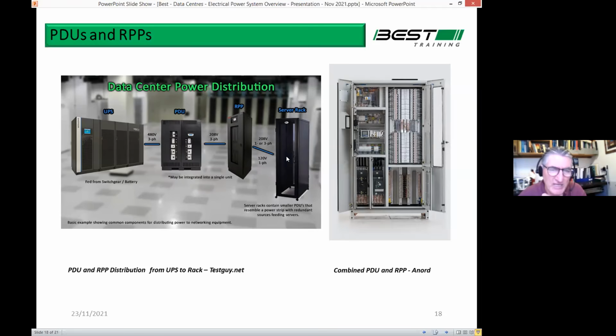The reason they do it that way in America is because they have 2 different voltages at low voltage. They have 480/277 as one voltage system, and then they have a lower voltage again for smaller power, which is 208/120. We don't have that in Ireland. So the PDU, which has a transformer in it, we're using that term in Ireland, but it's not really a PDU because we don't have a transformer in it. So again, I won't get bogged down with that, but that's the typical arrangement.